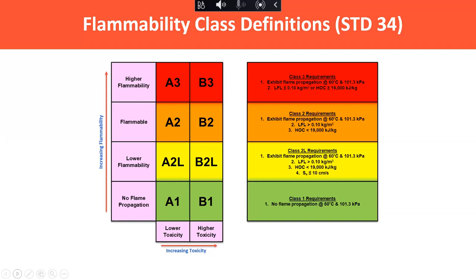So a big world of difference between those two refrigerants. And where we're really talking here, moving as an industry, is into this 2L, A2L category, sometimes referred to as mildly flammable or lower flammability. They are very different. There's a lot of things similar to the A1s, the non-flammables, but other things need to be considered. One takeaway I want you to get today is what's changing, what's not, what you have to do differently, and what's going to be the same, because the A2Ls are the refrigerants we're going to be dealing with a lot going into the future.